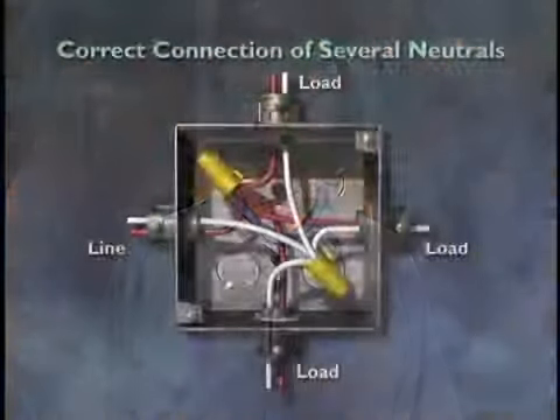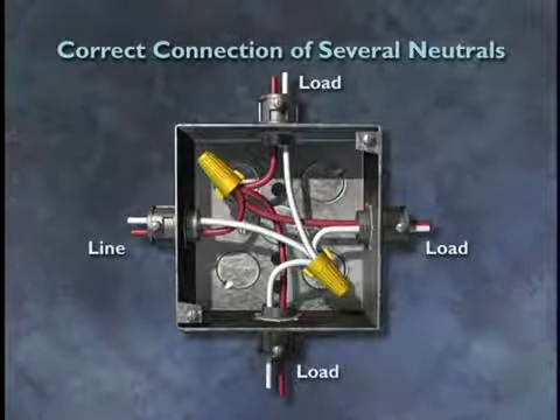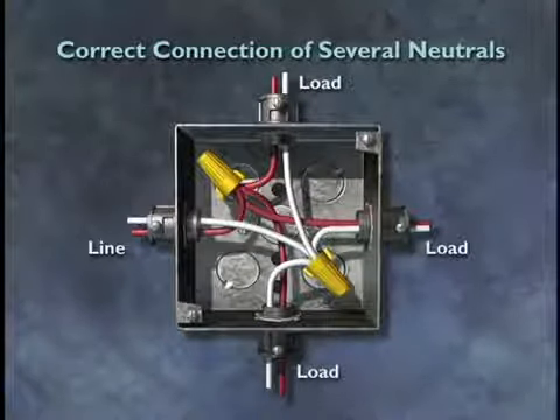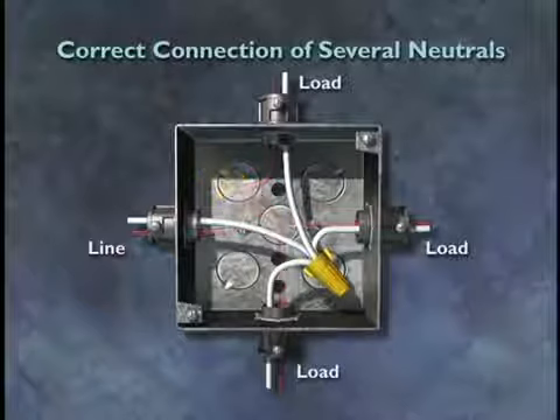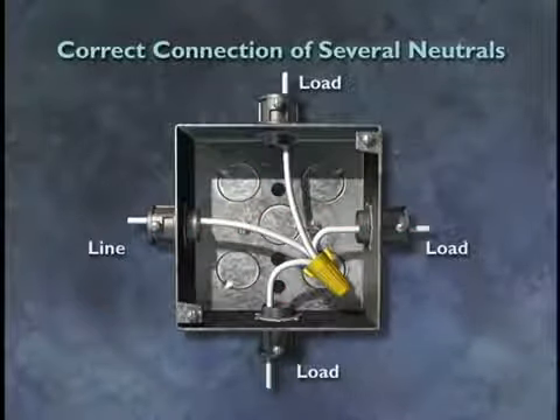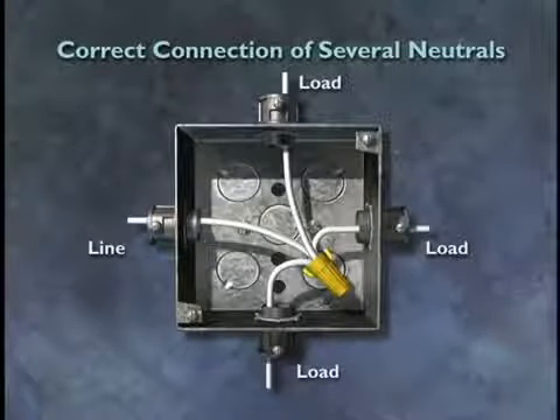Now, the obvious question at this point is, how should the neutrals in that junction box have been connected? The answer is to use two wire nuts instead of one. Connect the load neutral to its own supply neutral and not to the other branch circuit neutral. Here is how the correct wiring looks inside a junction box serving one branch circuit. In most junction boxes, all neutrals may be joined since only one branch circuit feeds all loads.